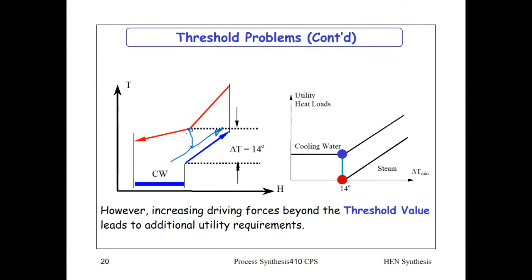And then the heat exchanger between these two, the cold and the hot stream, the process heat exchanger, has a lower log mean temperature difference for the exchanging of the process streams than if you used delta T equals 14. So you'd want to push the DT min to its maximum. Yeah, exactly, to reduce the heat exchange area. That's precisely it. So there's no sense in taking this point any further than underneath the hottest part.